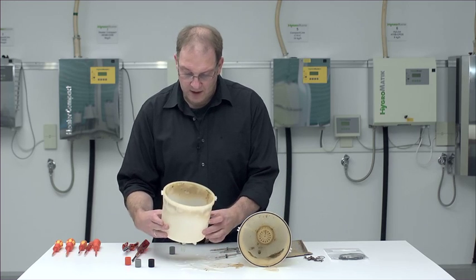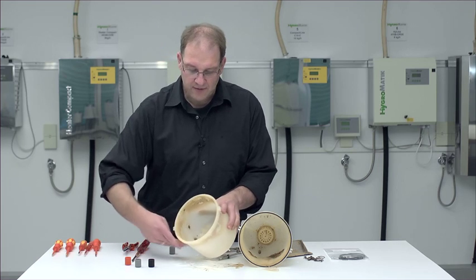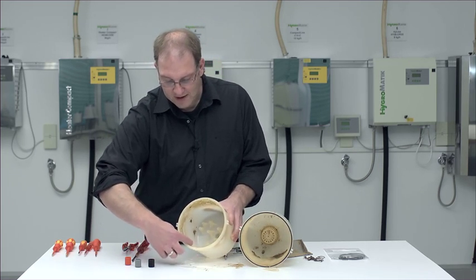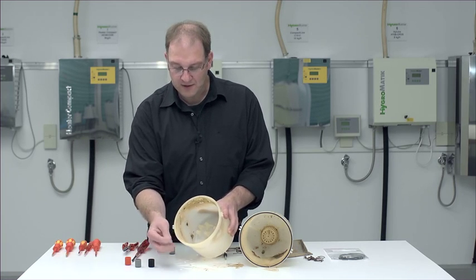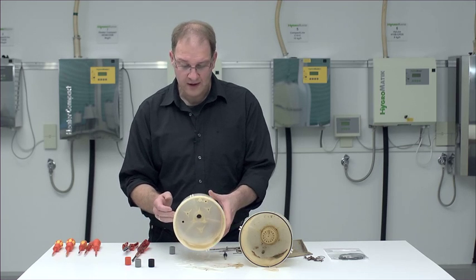To clean the electrodes, I would now use a putty knife or other tool and simply scratch down upon the surface. We currently have here a kind of lime scale formation. This I can get rid of quite easily with my fingers. It is, however, in its present degree of development not at all bothersome.